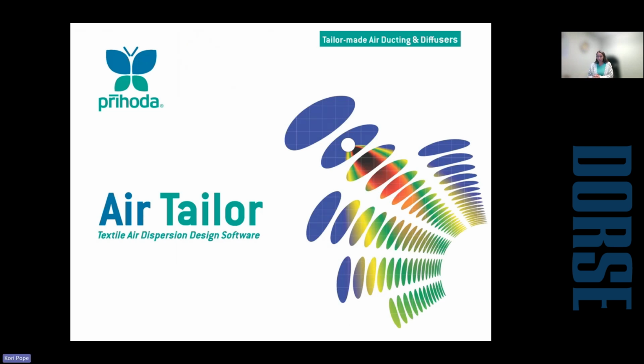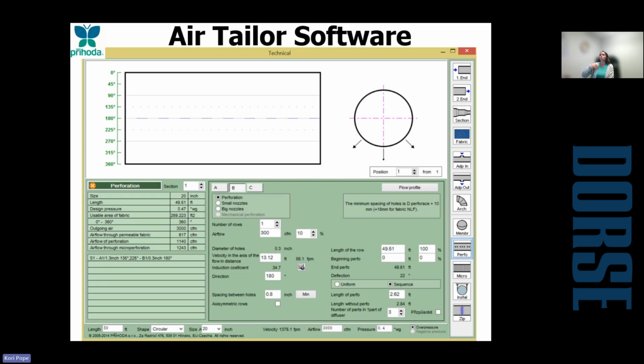So now to date, Prihoda's greatest invention is the software that we actually use to design every parameter of the fabric duct system. And this is the software that we call Airtailor. So as we're putting in every parameter of the job itself, we get to look at every elbow, make sure there's no vibration. We get to select your fabrics and the hold open and all of that. But one of the tabs that we spend the most time on is actually the air distribution tab. So this is where we're putting in your perforations or your micro perforations, your nozzles, to make sure we're getting the proper velocities at certain distances from the ducts.